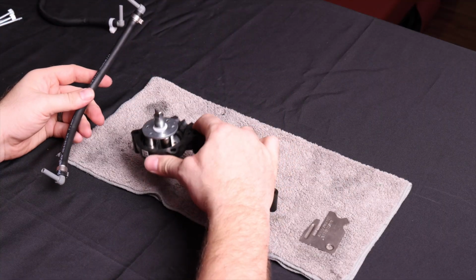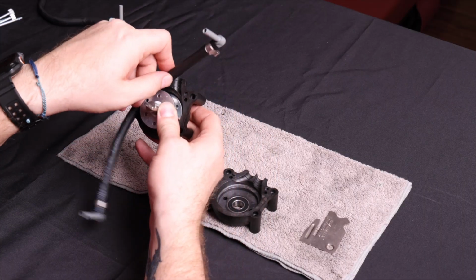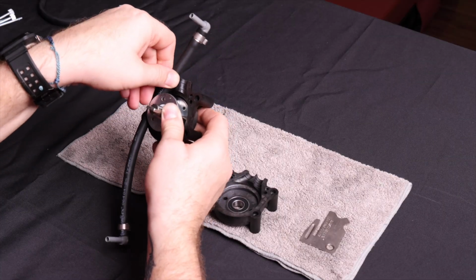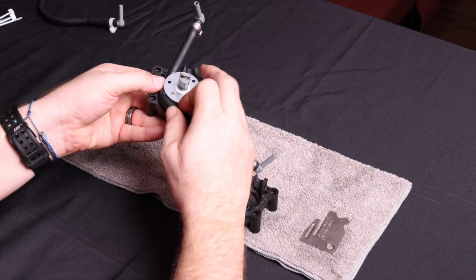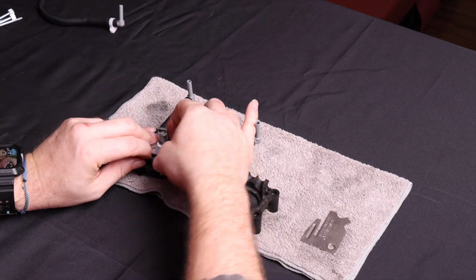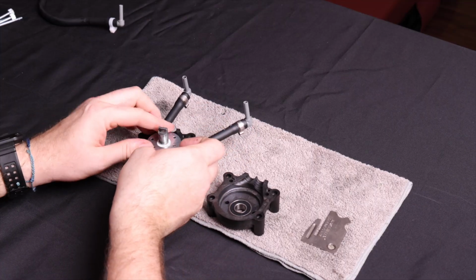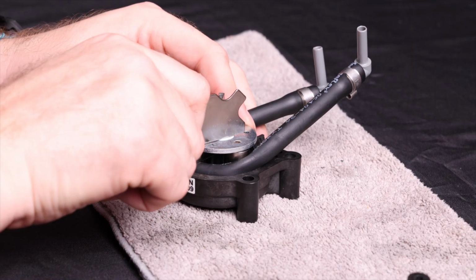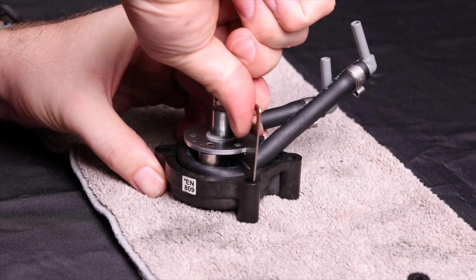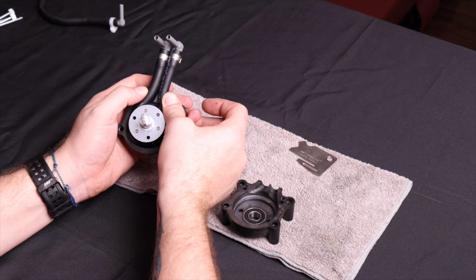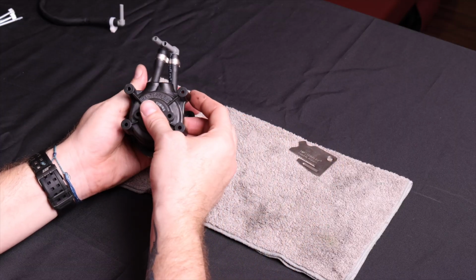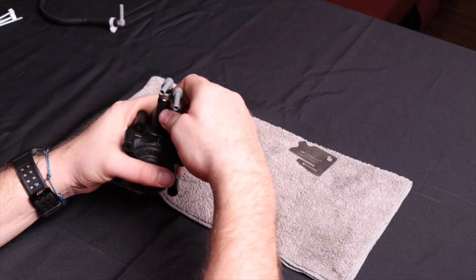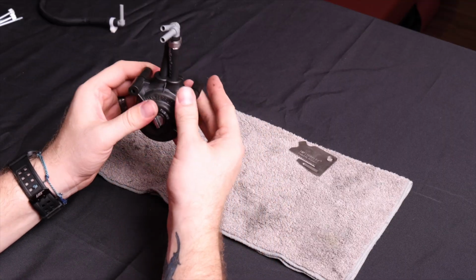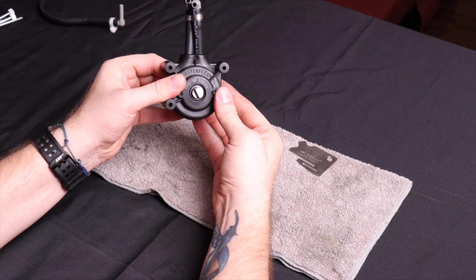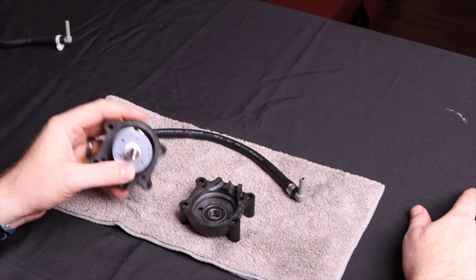Take your new tubing and the top portion of the bell assembly. Place the tubing with the elbow facing up about halfway into the pump. Gently push the tubing past one of the bearings into the crevice. Take your key and slide over the shaft assembly. Rotate and remove your key. With the tubing in line and the elbows facing up, we can now add the bottom portion of our bell. Being careful not to pinch the tube between the bell. And squeeze tightly.